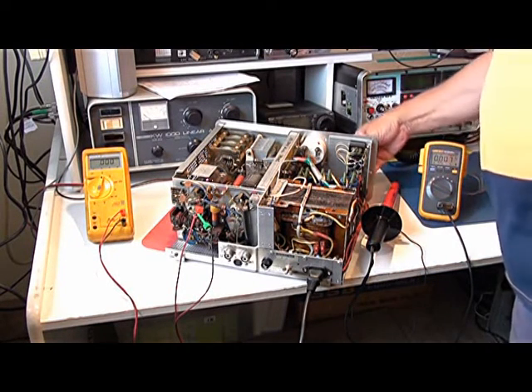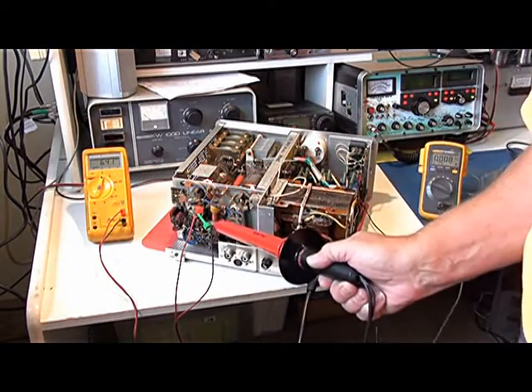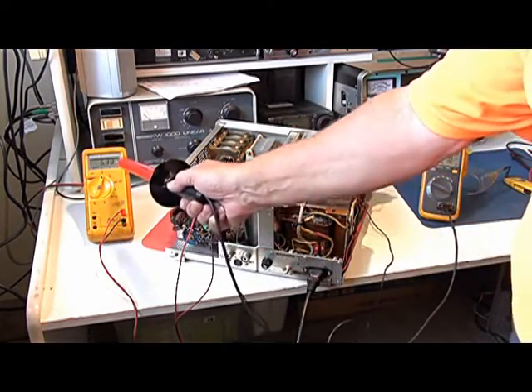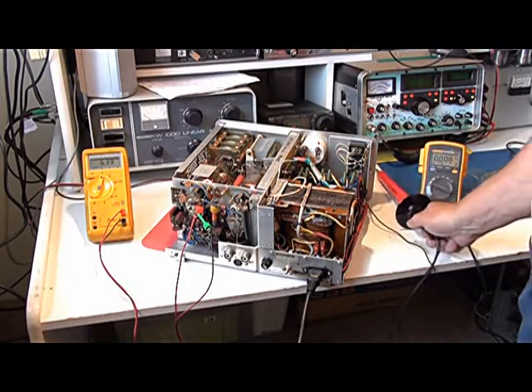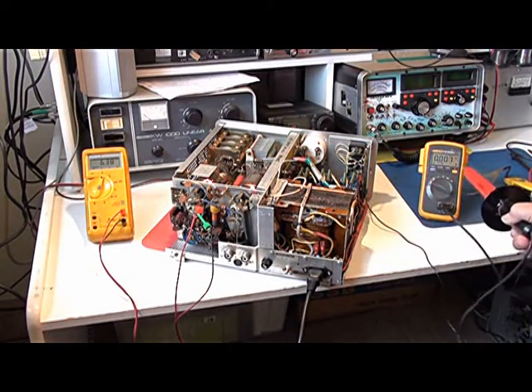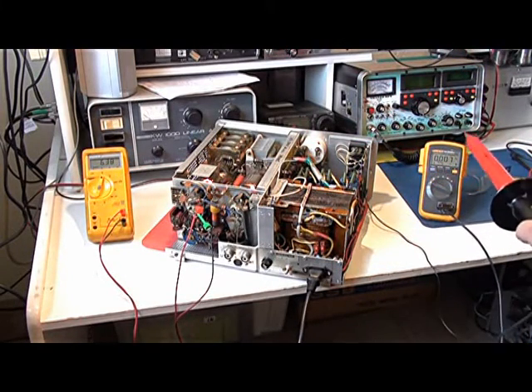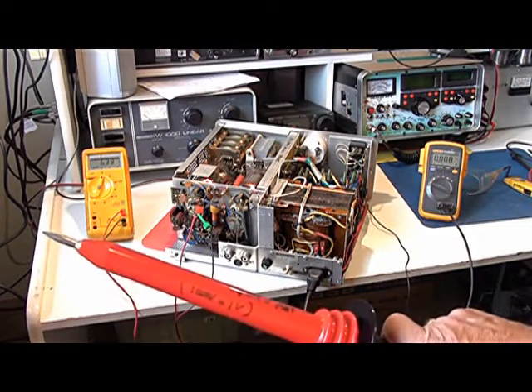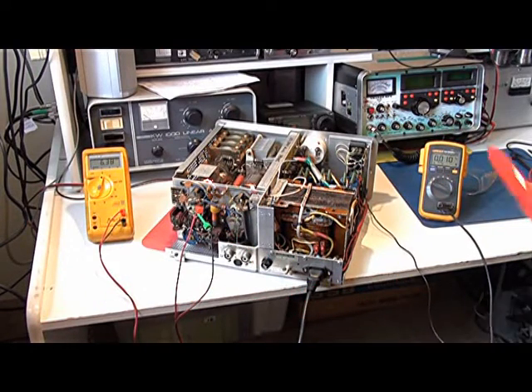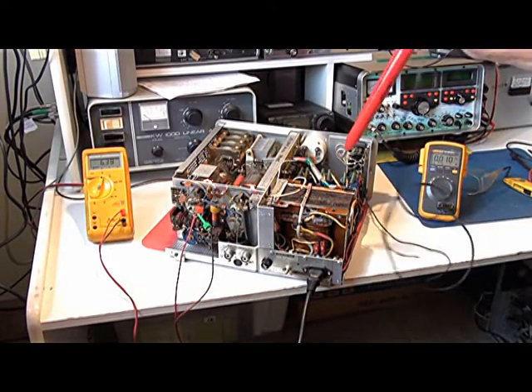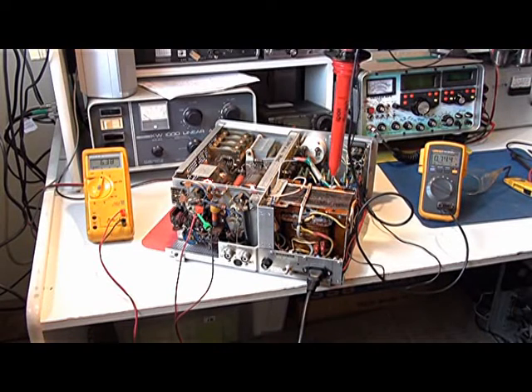So I'll turn it on, and I have the meter here. That's on the filament voltage, and it's showing 6.38 or thereabouts. And over here I have the meter with the 1000-to-1 probe on the EHT output. I'll just measure that - we're looking at 746 volts.